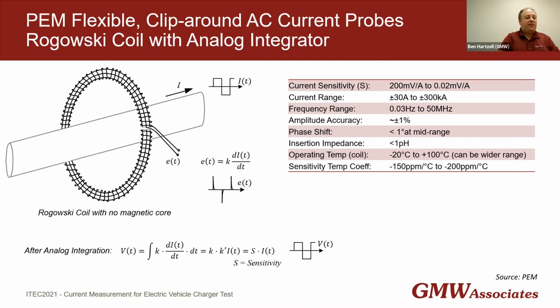As DC current has no rate of change, DC current does not induce a voltage in the coil. Rogowski coils are completely insensitive to DC. Here we're going to look briefly at the specifications of PEM Rogowski coils. You can see current ranges anywhere from 30 amps to 300 kiloamps, frequency ranges of 0.03 hertz all the way up to 50 megahertz. It's specific ranges depending on the model.